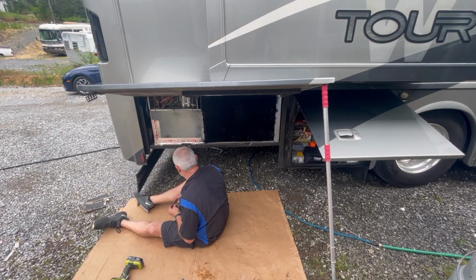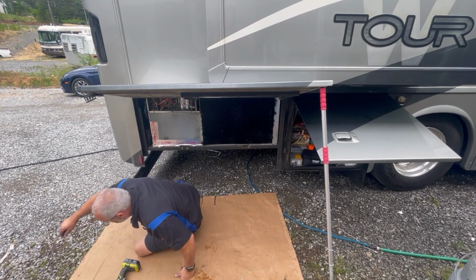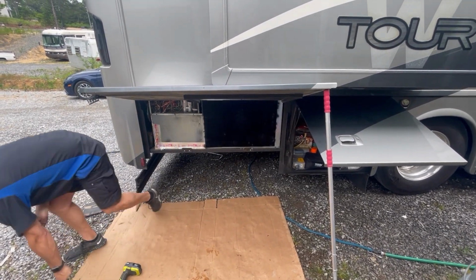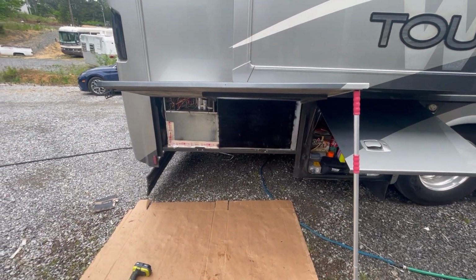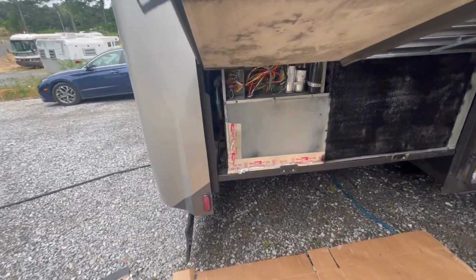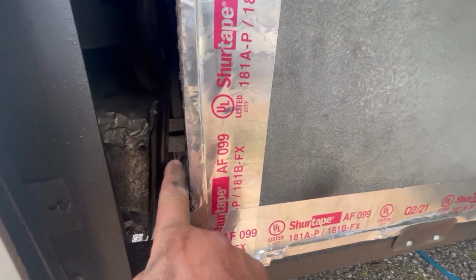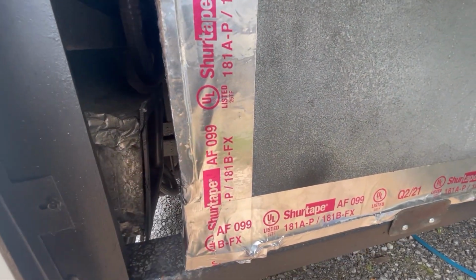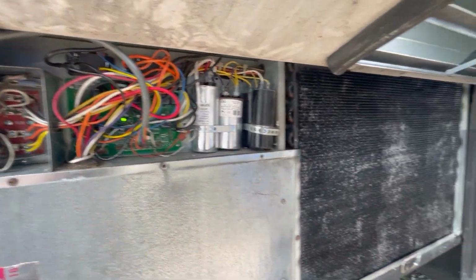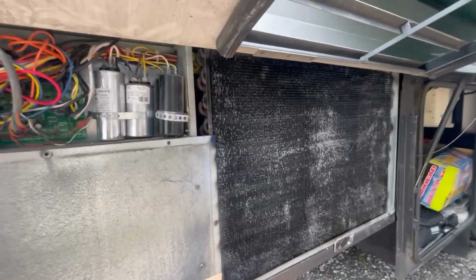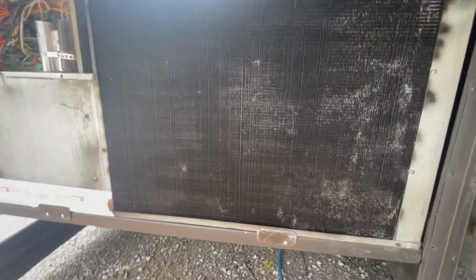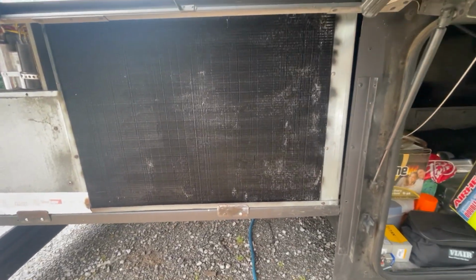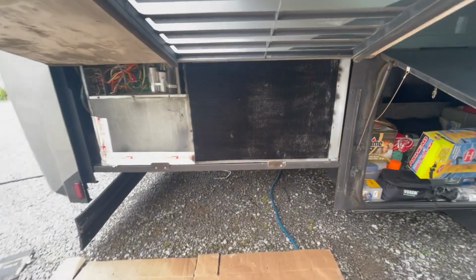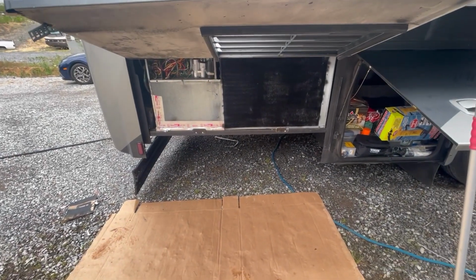We've got the basement air all tested and ran - it ran great, all the amp draws were good. Now Lewis is getting everything bolted back up inside of it. Just have a little bit of duct work left to do with the return, got to get that back in place and taped up, and all the wiring back in place. The coils are all straightened out from where the last guy bent them all over - even threw a little spray paint on them to make it look nice. So it's ready to go back in, and we're going to retest here in just a minute.